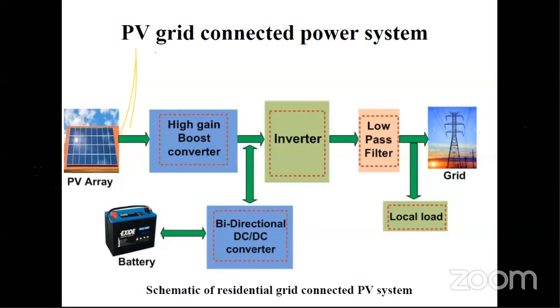First, you need to step up with a DC-DC converter. The reason is, if you want 230 volts AC, at least on the inverter side, the DC link should be at least 350 volts.